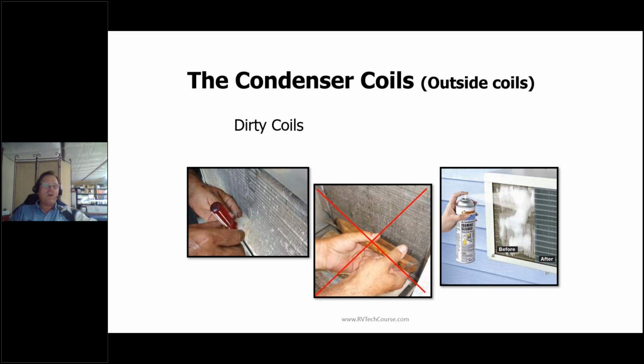So the compressor's running well, the blower's running well, but we're not getting rid of the heat because the fins are bent and they're blocking the airflow. So many times you just take a little fin comb and you just comb them out. Just be very gentle with them and save the air conditioner.